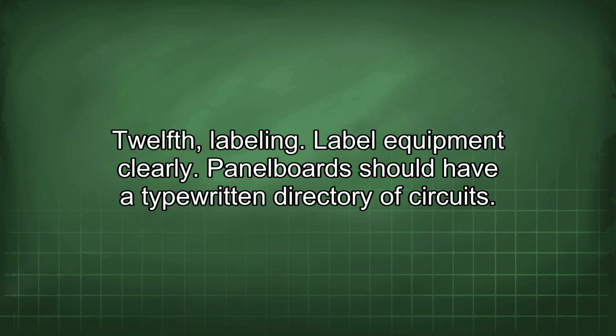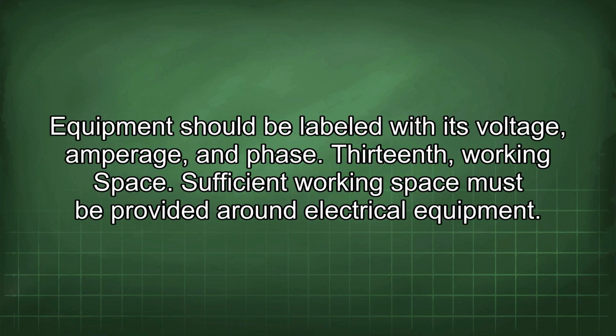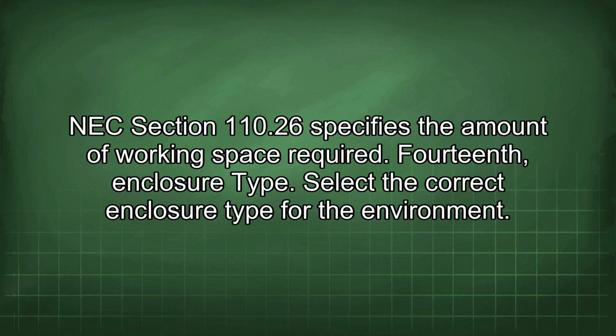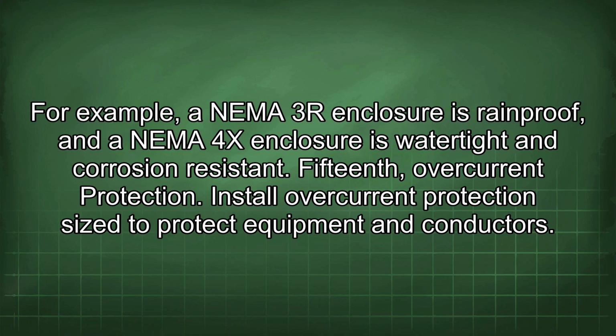12th, labeling. Label equipment clearly. Panel boards should have a typewritten directory of circuits. Equipment should be labeled with its voltage, amperage, and phase. 13th, working space. Sufficient working space must be provided around electrical equipment. NEC Section 110.26 specifies the amount of working space required. 14th, enclosure type. Select the correct enclosure type for the environment. For example, a NEMA 3R enclosure is rainproof and a NEMA 4X enclosure is watertight and corrosion resistant.